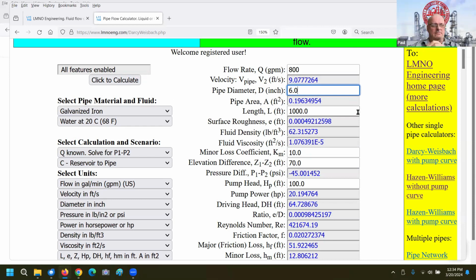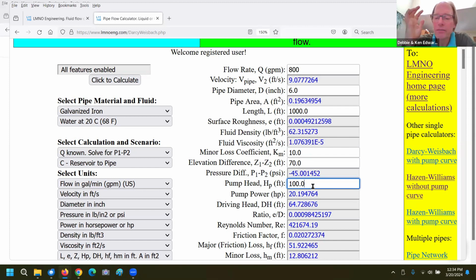Yeah, good point. A lot of times people will be asking us for the pump head. We just had a client the other day who wanted to know the pressure coming out of his system. It was an air system, just like a fan, a very low pressure system, and they were modeling from the outlet of the fan to the outlet of their pipe, which discharged to the atmosphere. Just think of it as like an 8-inch duct, maybe 200 feet long, and they wanted to know the pressure in the system. When I hear that, I ask, where do you want to know the pressure in the system? He was thinking, by default, the outlet of the pump. And that's fine if you want to know the outlet of the pump.